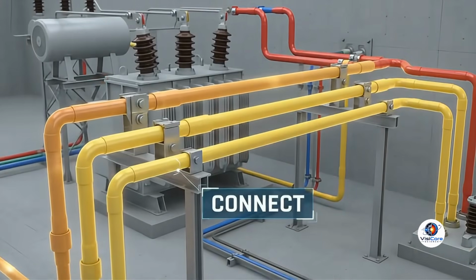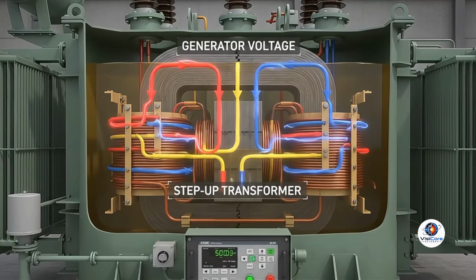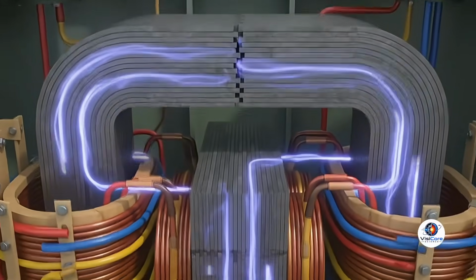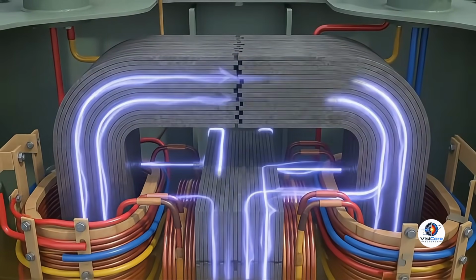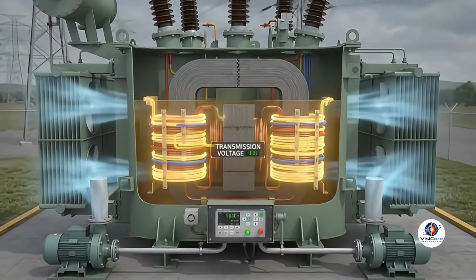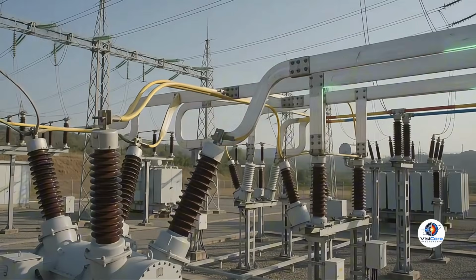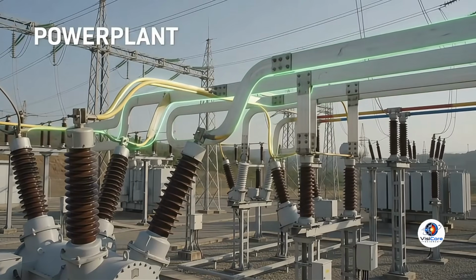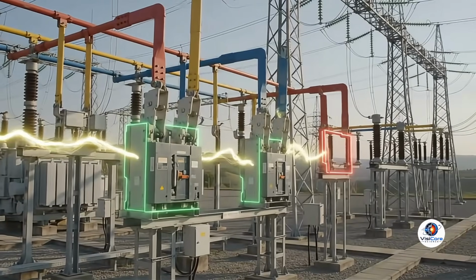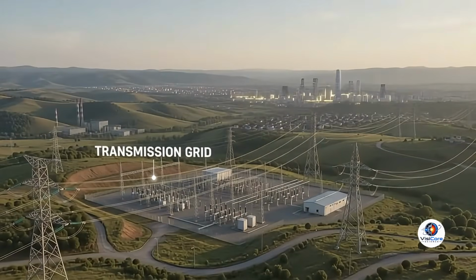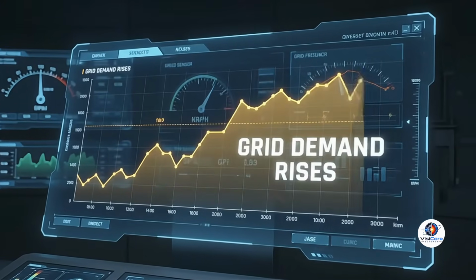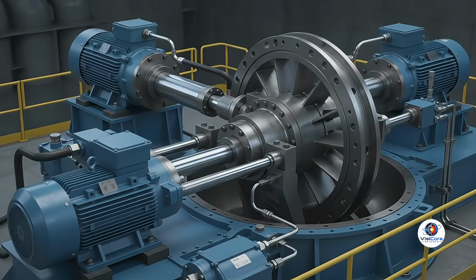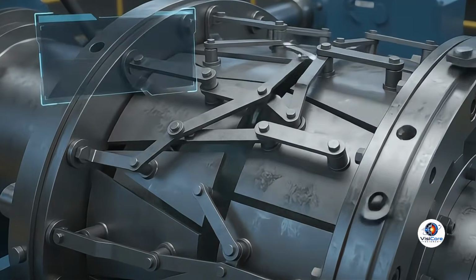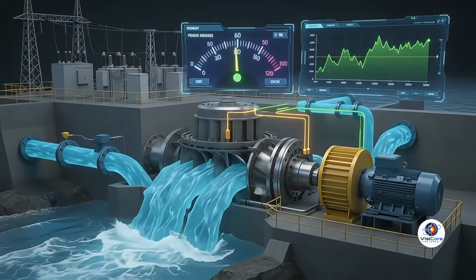The main breaker then closes. The transformer raises the voltage so electrical power can travel efficiently across long-distance transmission lines. From the switchyard, high-voltage electricity enters the interconnected grid and travels towards substations, industries, businesses, and homes. When electrical demand changes, the governor adjusts wicket gate opening. More water flow produces more turbine torque and greater generator output.